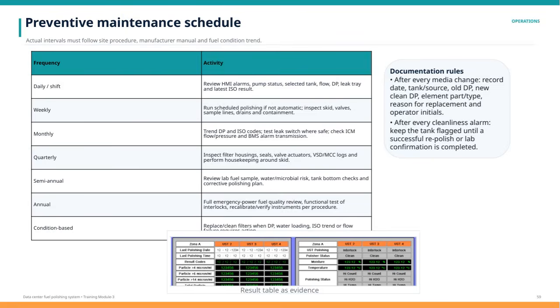Here we have a detailed preventive maintenance schedule designed to ensure optimal performance and reliability of the fuel polishing system. It's important to follow site procedures, manufacturer manuals, and fuel condition trends when determining actual maintenance intervals. Daily or per shift, operators need to review HMI alarms, pump status, selected tanks, flow rates, differential pressures, leak trays, and the latest ISO cleanliness results. Weekly tasks include running any scheduled polishing if not automated, and inspecting the skid, valves, sample lines, drains, and containment areas for any issues.